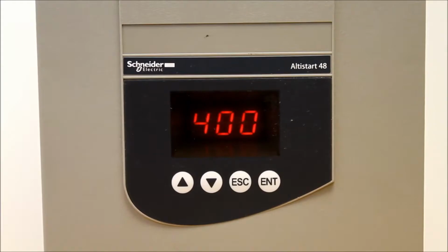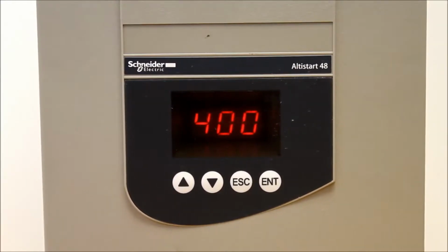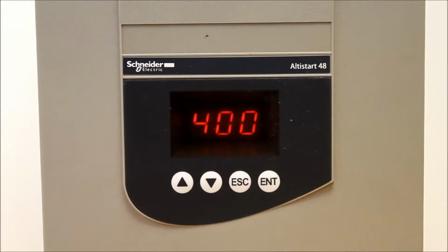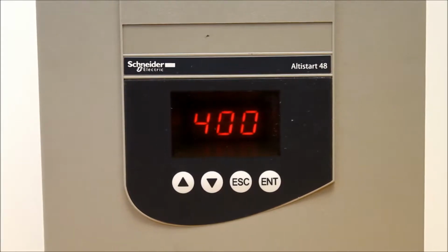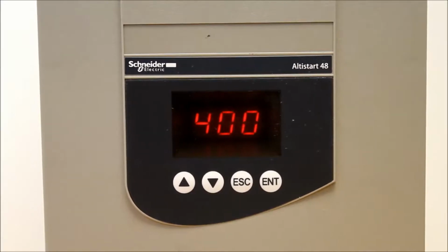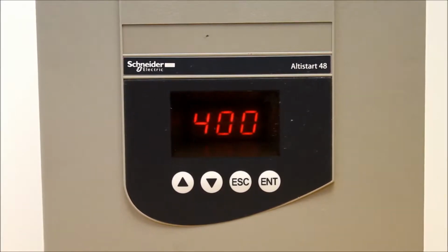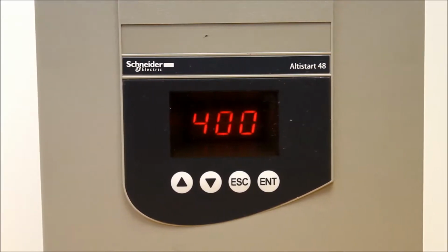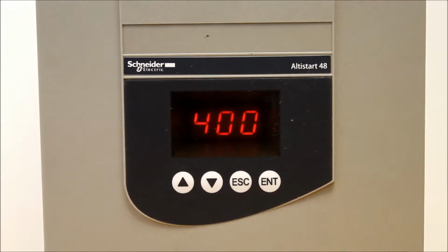Default is 400%, so that means that your motor FLA times 400% is the maximum current allowed by the soft start that the motor can pull. So let's say your motor is rated for 100 amps, just to make it easy, and you're pulling about 400 amps already, and it's still taking more than, let's say, 15 seconds to ramp up. If your motor is still having a hard time ramping up, way above that, all the way through your max start time, it will fault out.